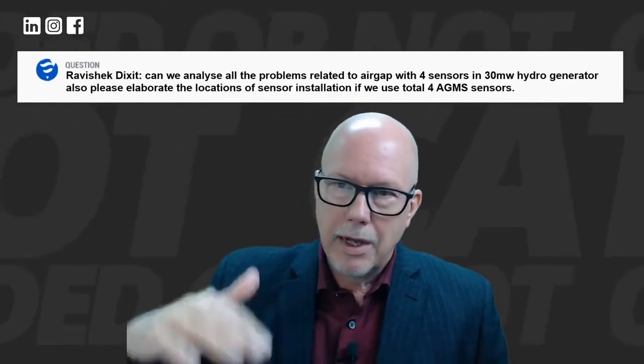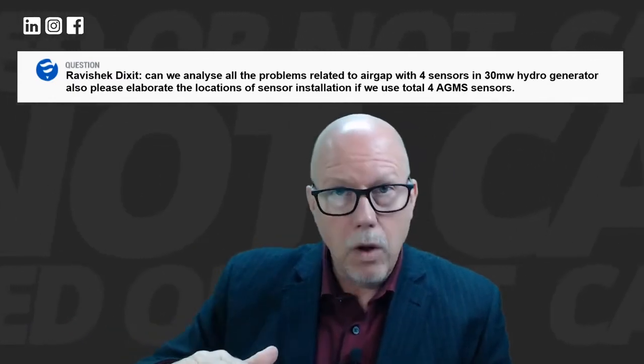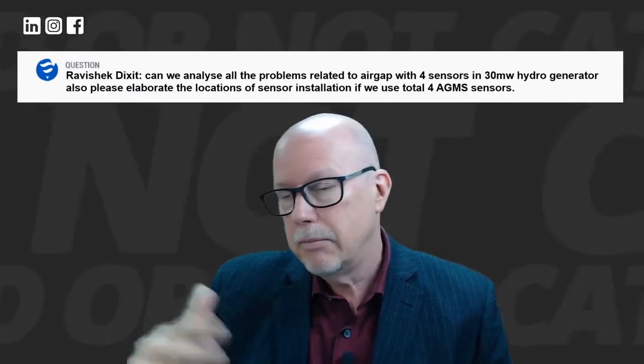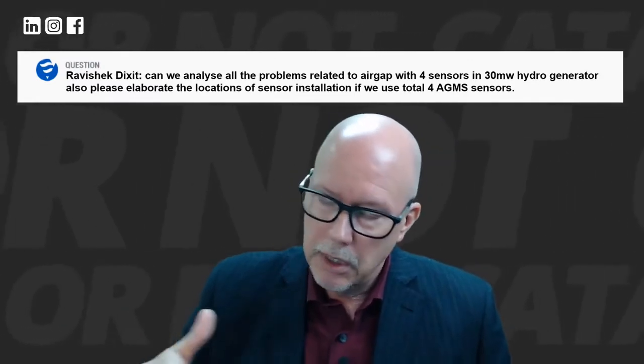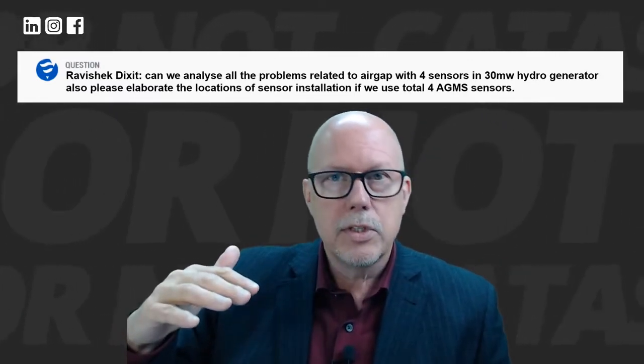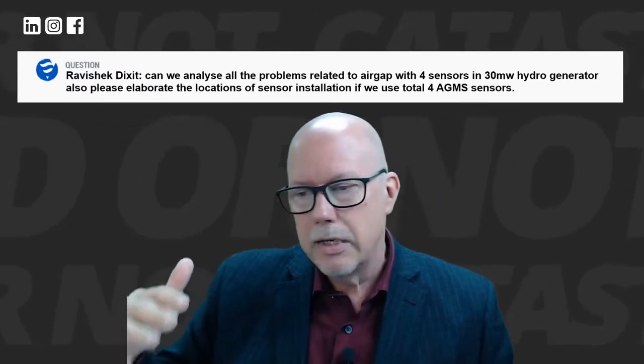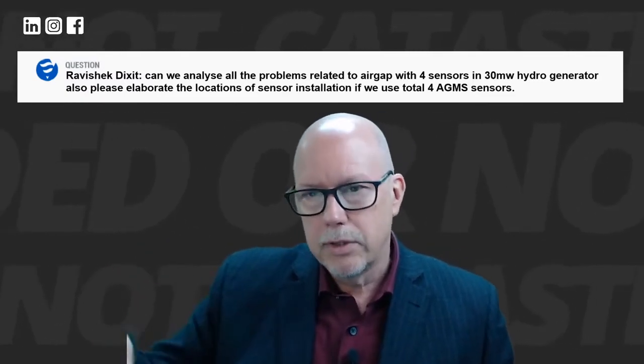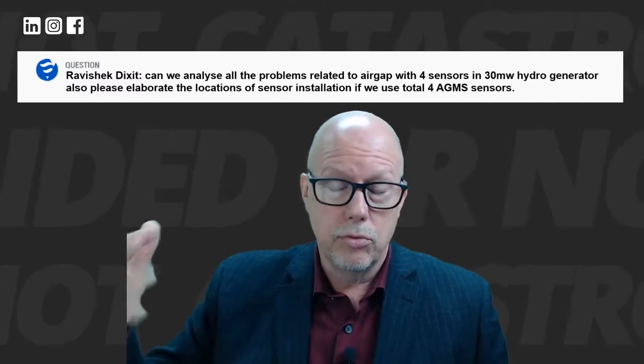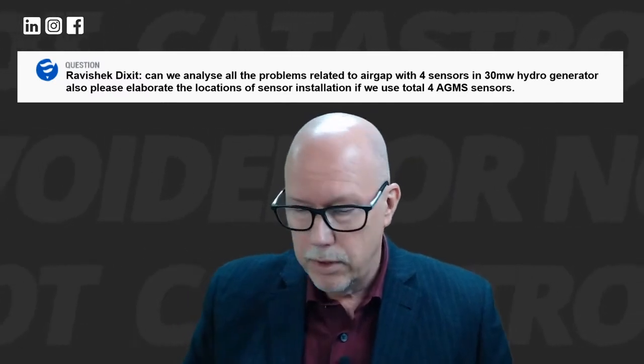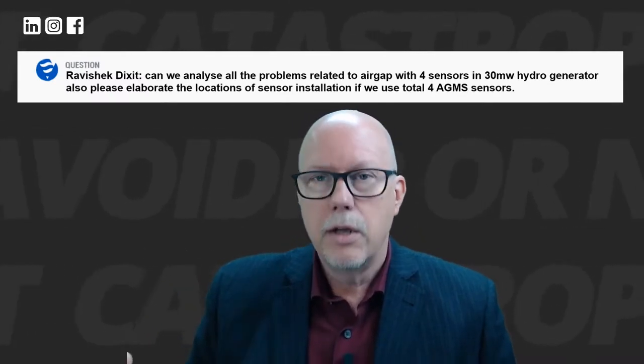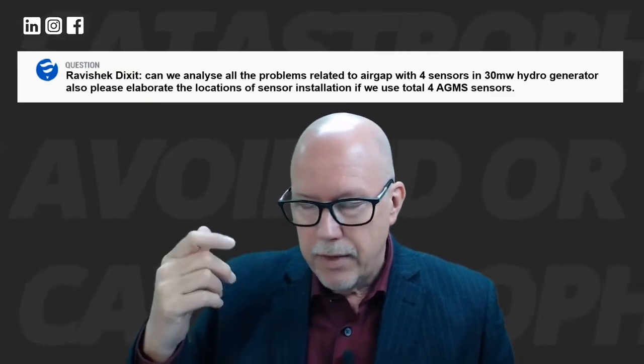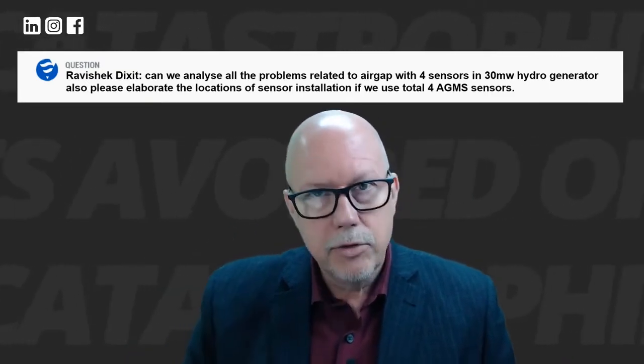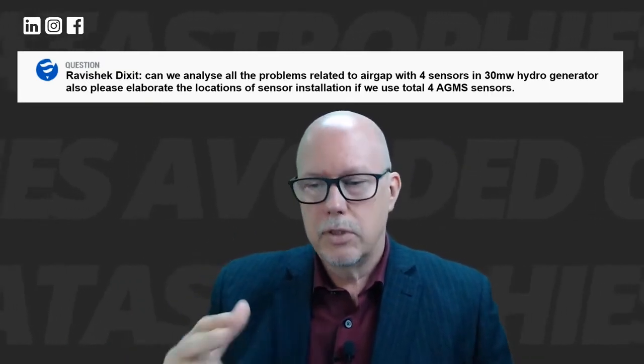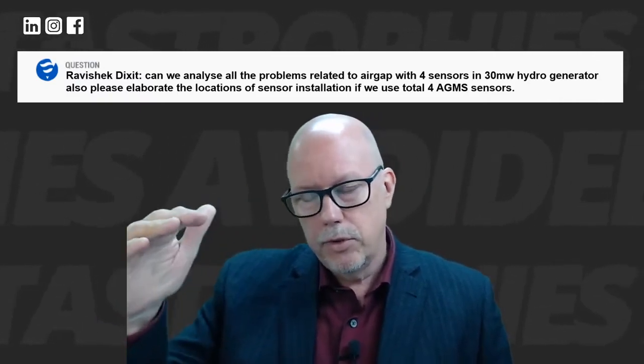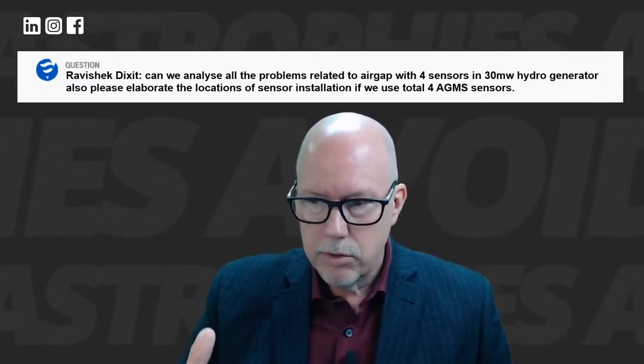And then you go into the height. If it's a very, very small unit, less than 1 meter high, maybe 1 level is sufficient. The higher the rotor size, hence the stator size, the more you have to go into multiple levels of sensors, at least 2, top and bottom. And as I mentioned with the other power station, they actually used 3. So the size of the unit will determine how many sensors. The height of the unit will determine if you're using top and bottom or middle sensors.